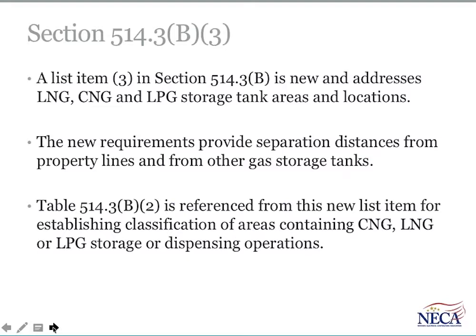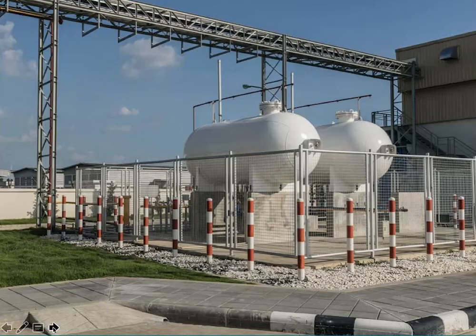It's not uncommon to see one of those tanks backed up to a property line, and if there's electrical equipment on the adjacent property, it could impact the classification of the area and the type of wiring method that is not controlled from the property on which the tank is installed. So there are distances there now that must be maintained from those property lines. And the image shows a typical large bulk storage tank for gaseous fuels.